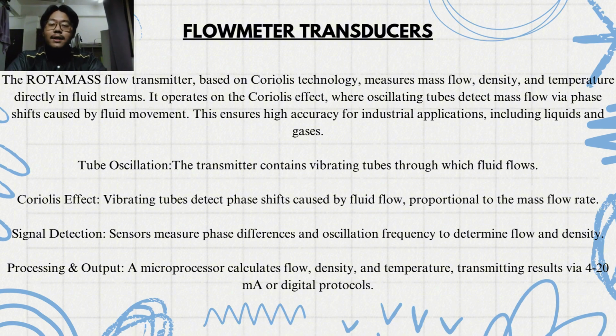So for the operating principle, first, tube oscillation. The transmitter contains a vibrating tube through which fluid flows. Second, Coriolis effect. Vibrating tubes detect phase shift caused by fluid flow, proportional to the mass flow rate. Then, signal detection. The sensor measures phase difference and oscillation frequency to determine flow and density. And lastly, processing and output. A microprocessor calculates flow, density and temperature, transmitting the result via 4 to 20 milliampere or digital protocols.